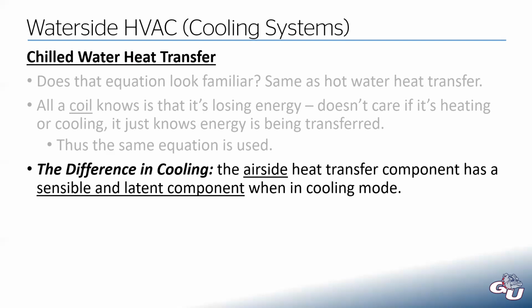And those two have to equal. Whatever is entering the water has to be leaving the air, or vice versa. But the difference in cooling is the air side has both a sensible and a latent component. So you'll have to think back to when we were talking about the HVAC introduction lecture and how that gets split, and how the sensible cooling is all about changing the temperature of the air. The latent is all about condensing water out of the air.